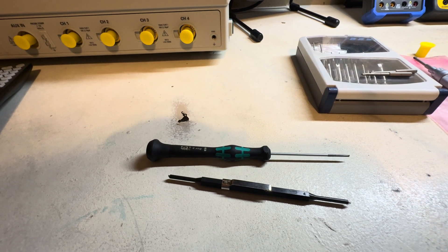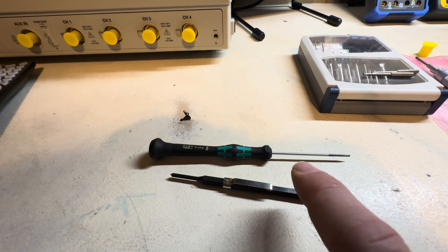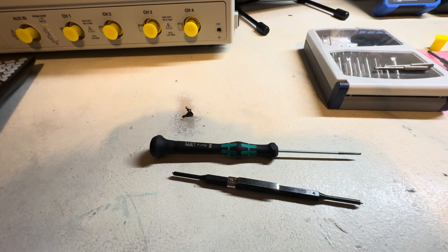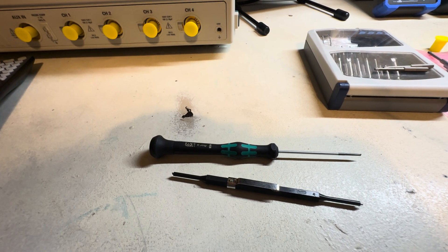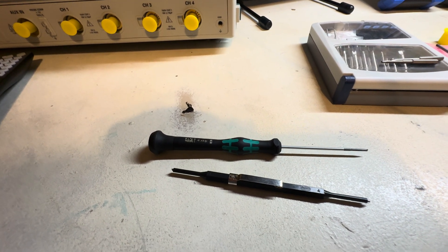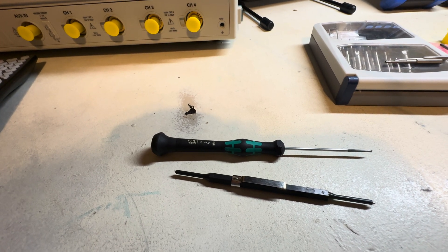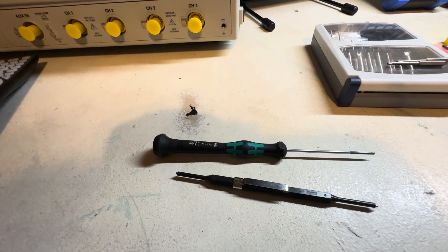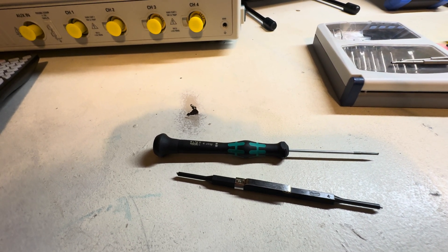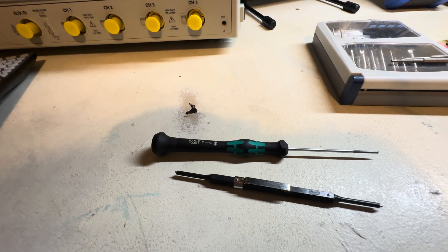One of the common mistakes I see when people do calibrations is using metal micro-screwdrivers to adjust the pots. The problem with that is you're actually creating capacitance just by touching it. You do your alignment, it looks perfect, then you take your hand and the tool off — and it goes back out. The reason is you're creating capacitance.